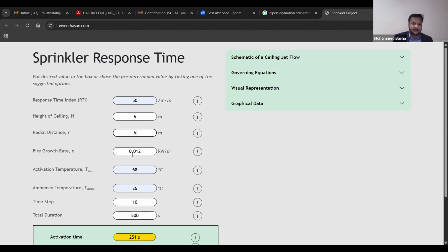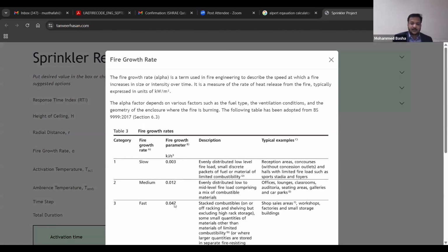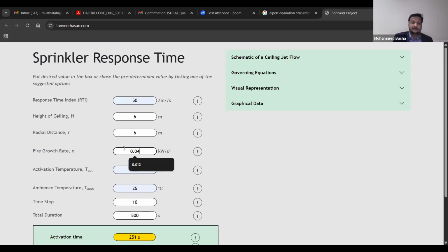Fire growth rate, alpha. Click this and you can see the same table I was showing you here. You need to see what this is: medium growth fire, fast growth. Let us assume it's a fast growth fire, 0.047. This is the value you need to put, 0.047. Activation temperature of the sprinkler is 68 degrees Celsius. Ambient temperature is 25 degrees.